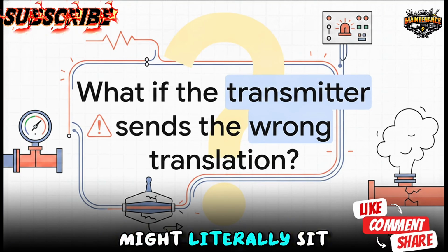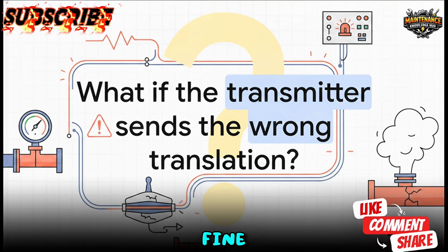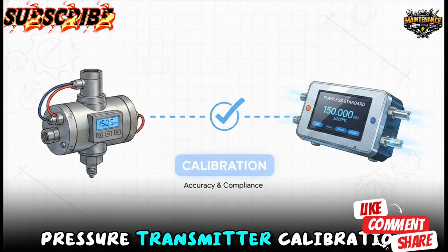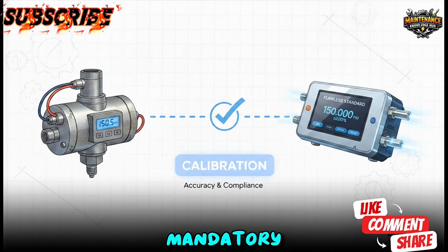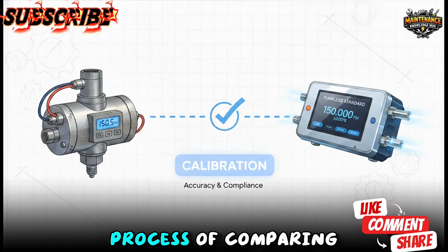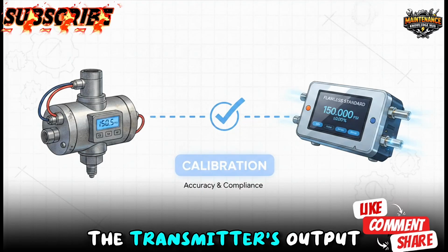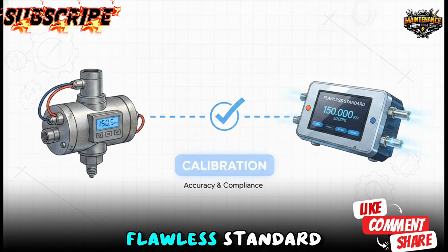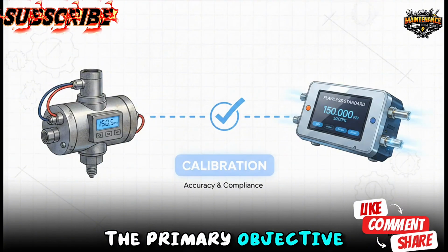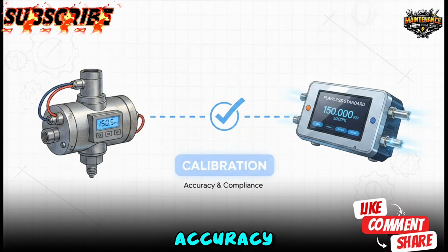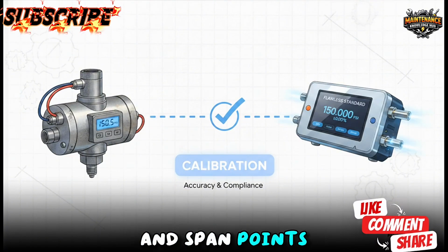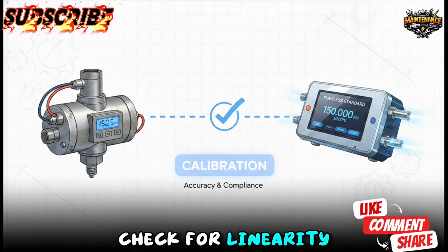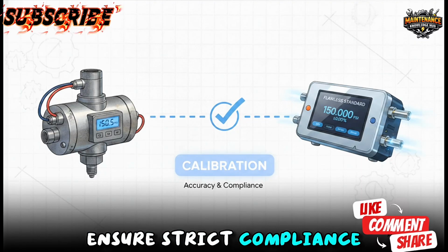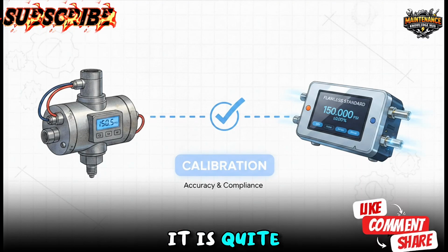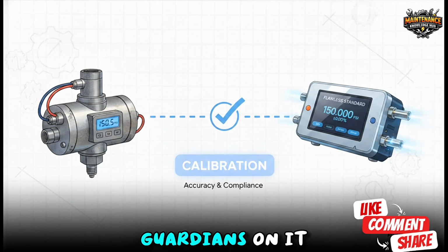The control room might literally sit there thinking everything is totally fine while a pipe is about to burst. And this is exactly why pressure transmitter calibration is absolutely mandatory. It's this meticulous process of comparing and adjusting the transmitter's output against a known, flawless standard. The primary objective of calibration here is to verify accuracy, adjust those 0 and span points if they've drifted, check for linearity, and of course ensure strict compliance with plant safety procedures. It is quite literally how we keep these invisible guardians on it.